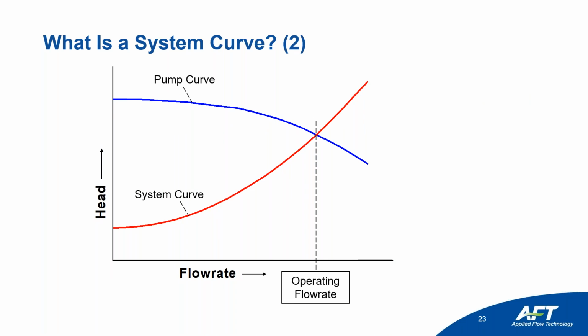The blue curve is your pump curve, the red curve is your system curve. Where they intersect, that's your operating point right there. Okay, so again, the system curve represents what pump head you need at each of these different flows. So you've got different flow rates, and as you have different flow rates, you've got resistances through your system. And as your flow rate increases, your system resistance increases.